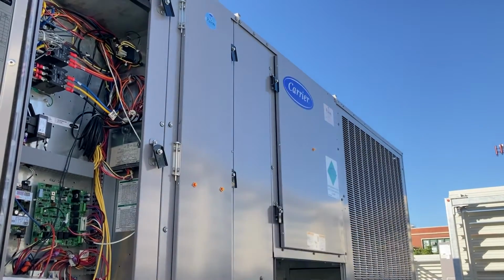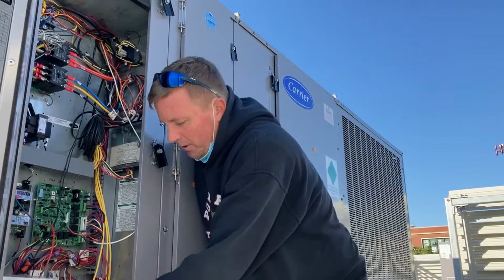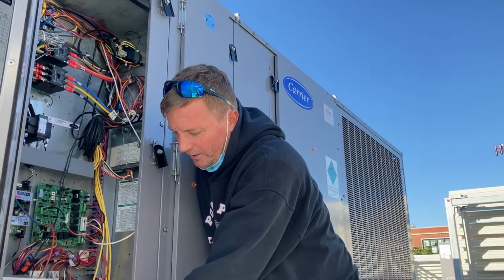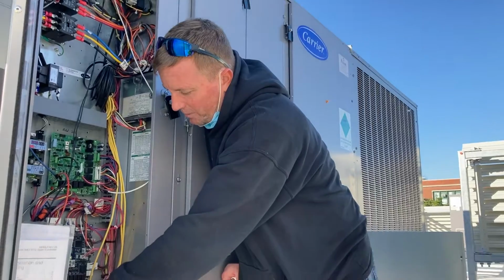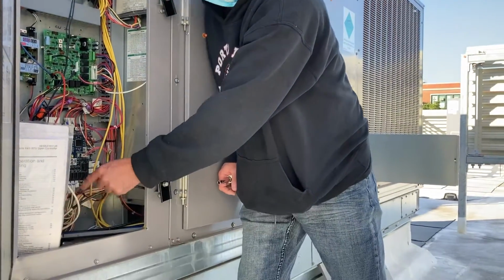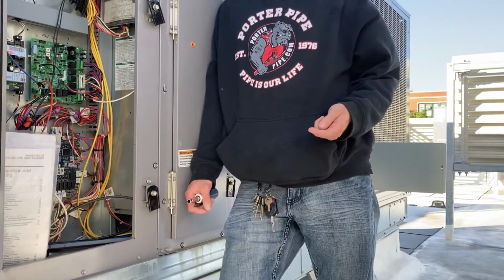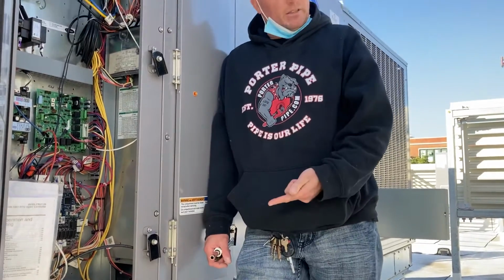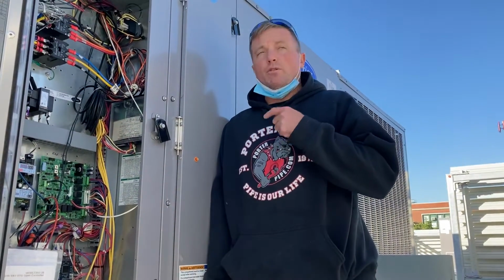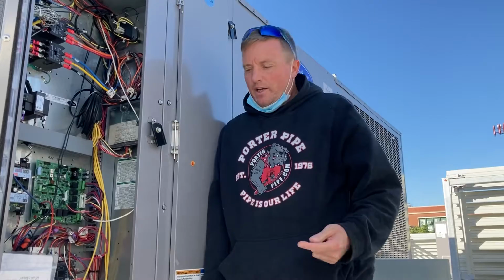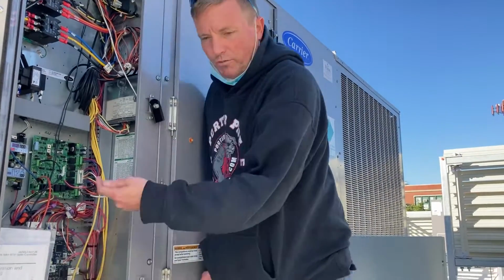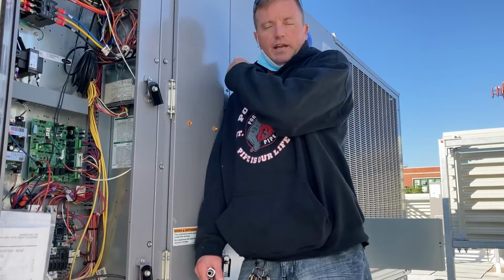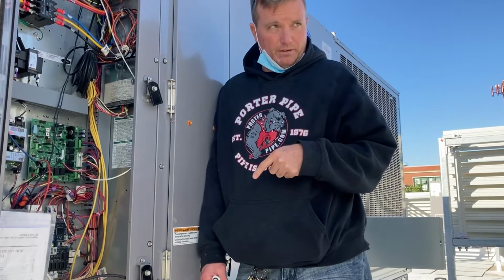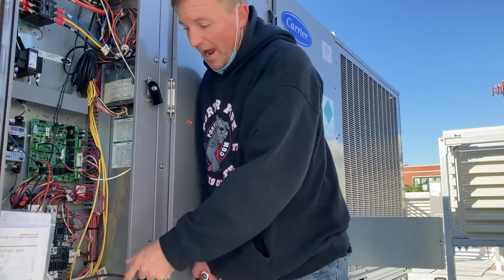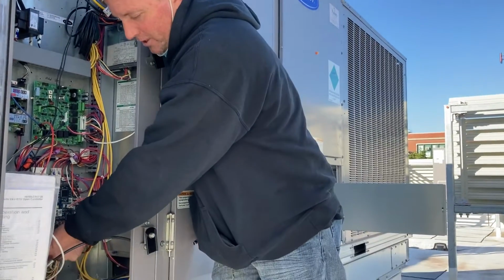You have a building pressure sensor, okay? Excuse me, you have a duct pressure. So this is our static. If anything happens as far as you're not feeling air, or the air is so violent it's like shaking stuff, it's because our pressure transducer is reading the pressure and saying to the fan, hey, there's no pressure down there, we need to speed it up, or there's a ton of pressure, slow it down. So if there's any kind of problem with that, this is what we want to check first.